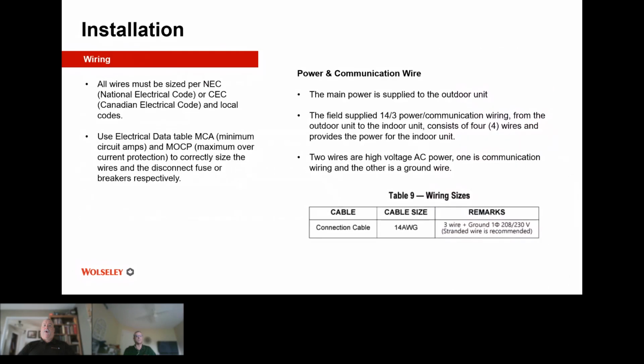Okay? Let's talk about wiring. All wiring must be sized to the National Electrical Code or the Canadian Electrical Code, or if your authority having jurisdiction has some special codes, please make sure you adhere to them. All of the manufacturers have the MCA, or minimum circuit amps, or the MOCP, the maximum overcurrent protection, clearly on their rating plate, which is on the outdoor unit or in the manual, so that you can be sure that you are putting the right one in.